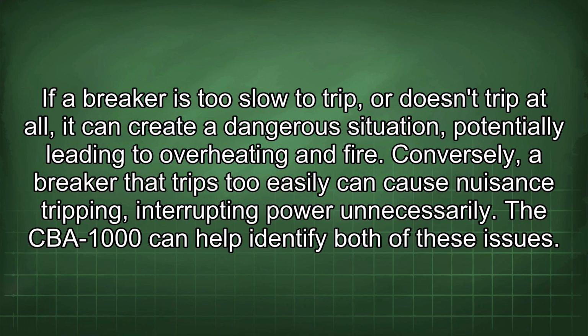If a breaker is too slow to trip, or doesn't trip at all, it can create a dangerous situation, potentially leading to overheating and fire. Conversely, a breaker that trips too easily can cause nuisance tripping, interrupting power unnecessarily. The CBA-1000 can help identify both of these issues.